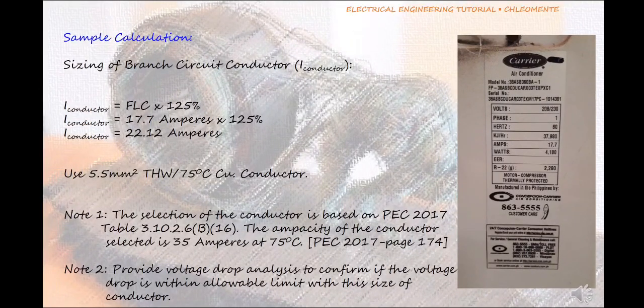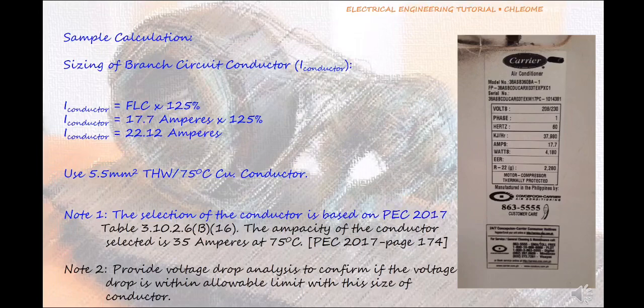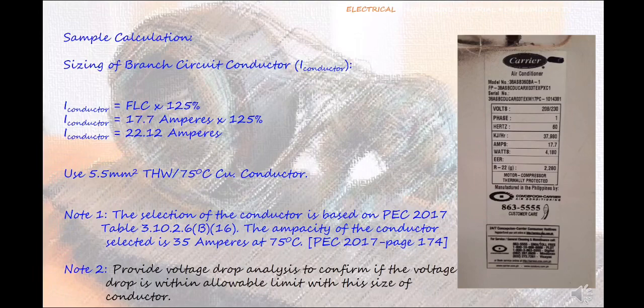Sizing of Branch Circuit Conductor. I-Conductor equals FLC multiply to 125%. I-Conductor equals 17.7 amperes multiply to 125%. I-Conductor equals 22.12 amperes. Use 5.5 square millimeters THW slash 75 degrees Celsius copper conductor. Note 1: The selection of the conductor is based on PEC 2017 Table 3.10.2.6(B)(16). Note 2: The ampacity of the conductor selected is 35 amperes at 75 degrees Celsius, PEC 2017 page 174. Note 3: Provide voltage drop analysis to confirm if the voltage drop is within allowable limit with this size of conductor.